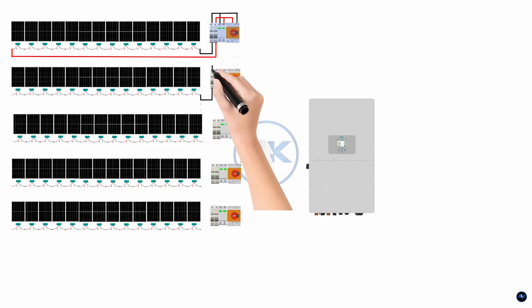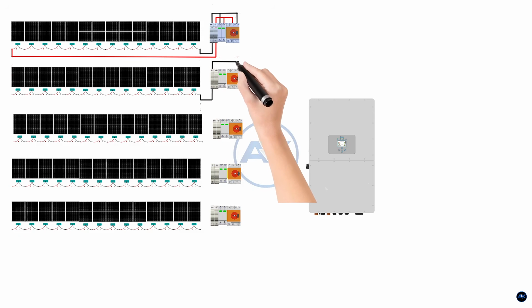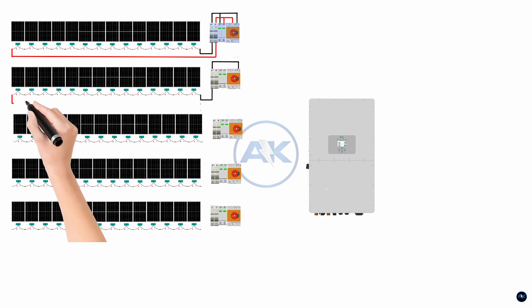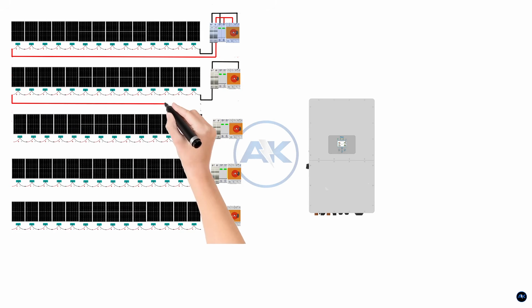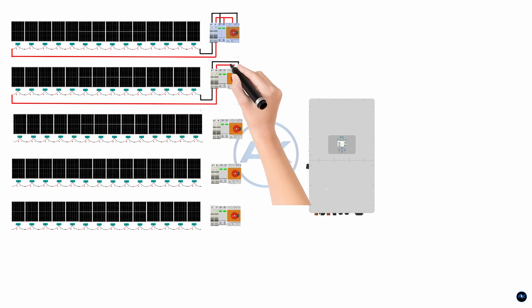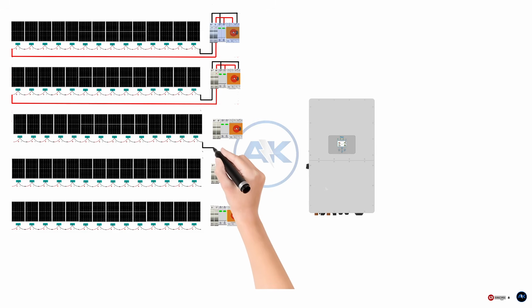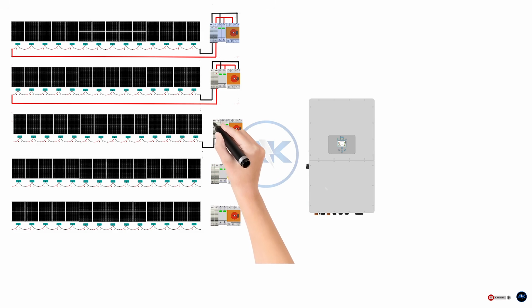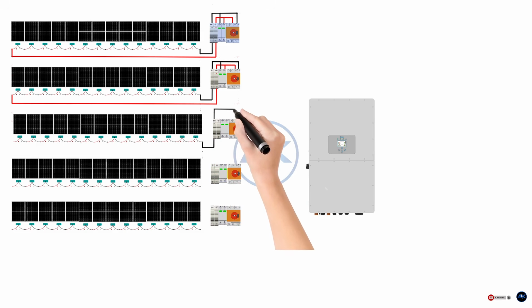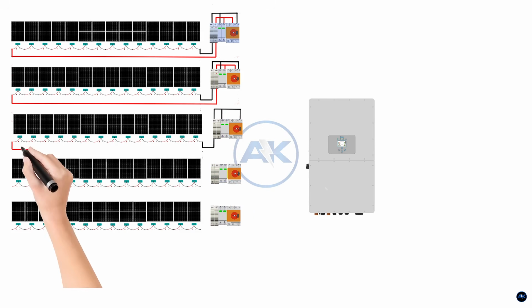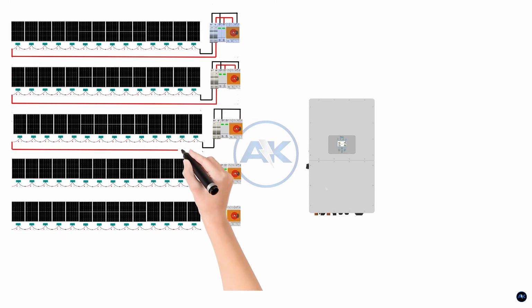Let's start with the first string. Place 14 panels in a line. Connect the positive terminal of the first panel to the negative terminal of the second panel. Then connect the positive of the second panel to the negative of the third panel. Continue this same pattern until all 14 panels are connected in series. When the string is complete, you will have one free negative cable at the first panel and one free positive cable at the last panel.